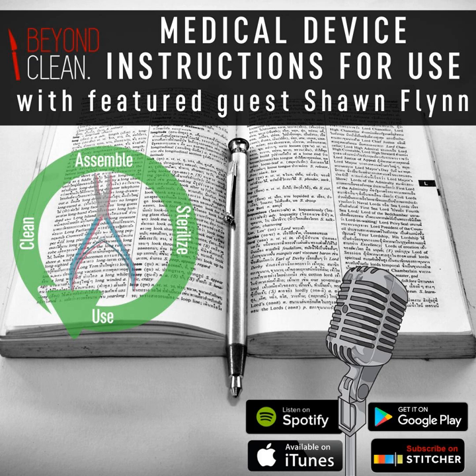The interesting thing with validations with lab work is that there are a number of labs across the country that do it, and depending on the complexity of the device and the relationship between the manufacturer and the lab, you can get labs that are more lax or lenient than others. I won't name any names, but if you have a very complex device, theoretically you're not supposed to teach to the test. So if your device fails validation, you go back into development mode to refine the device, mitigate, so it could actually clear a sterilization and clean validation appropriately. But some labs, I've been told, will modify their test sites so it doesn't necessarily create a worst case scenario.